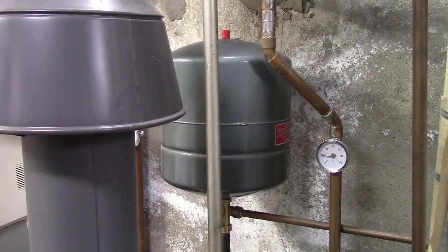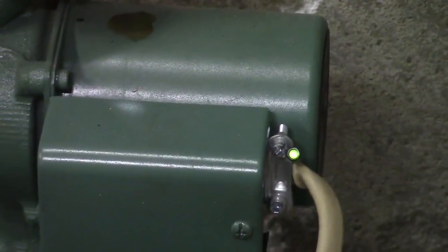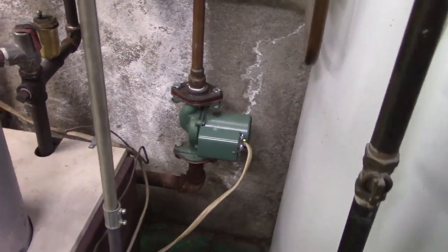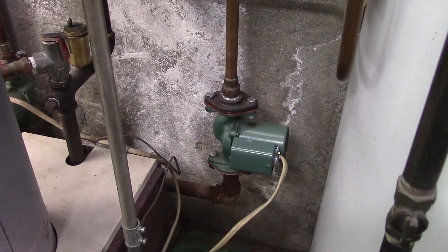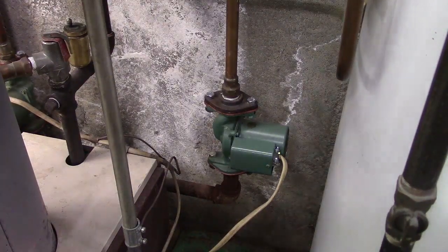That means the circulators are circulating, which is a great thing. And the next step is to fire it up. But I like to leave the circulators run. You can see I have indicators on them. A little green LED, and there's one on the other one. There's a video about that. There's a link in the description. This way I know which zone is calling for heat when I'm down here, which is really a nice touch. Should be on all boilers, but hey, this is my house. Everything looks good. I'm going to let these circulators chooch for a bit.